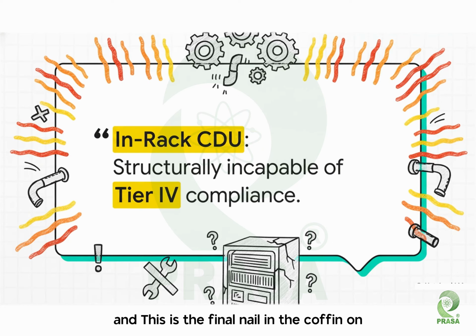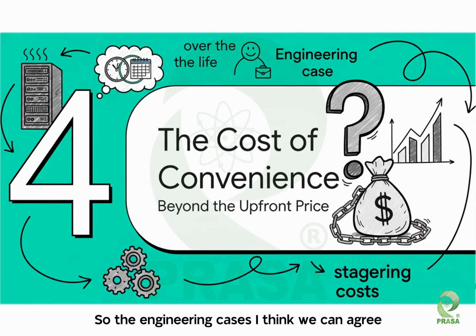And this is the final nail in the coffin on this subject. It's not just that the in-rack model fails the Tier 4 test, it is structurally incapable of ever passing it. The very design philosophy, cramming the entire cooling system inside the IT rack, makes true fault tolerance a physical impossibility. So, the engineering case, I think we can agree, is pretty open and shut. But what about the practical, day-to-day side of things? The main argument you hear for in-rack is always about convenience. But that convenience comes with some really staggering hidden costs that pop up over the life of the data center.